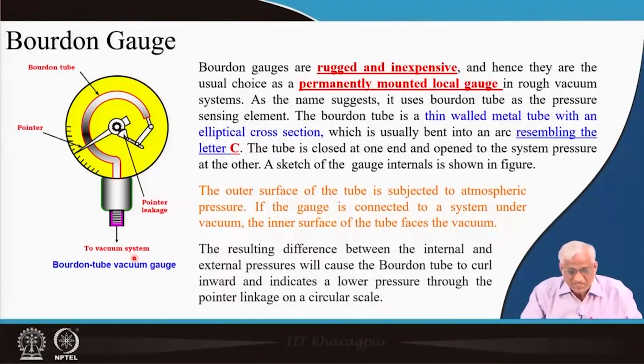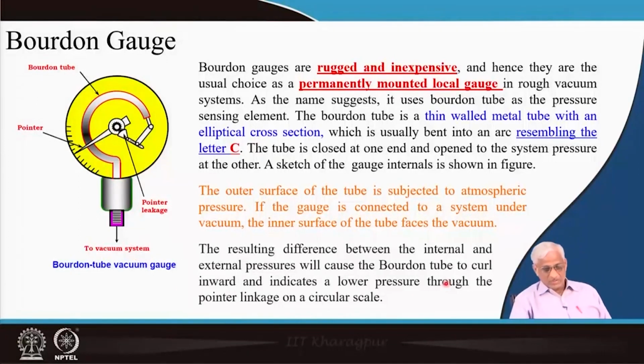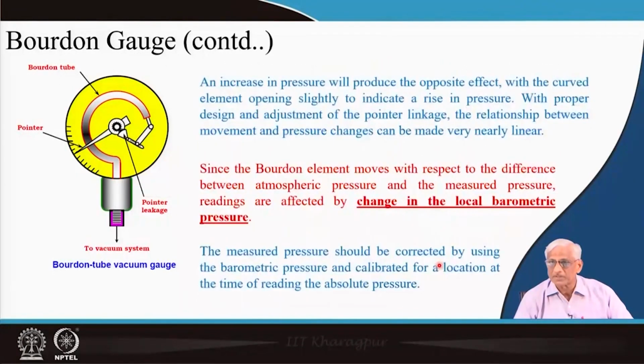So these deflections are finally measured and calibrated using a primary sensor like a U-tube manometer at fixed points. Then you can use it left and right in a very rugged way. The resulting difference between outer and inner pressure is the fundamental principle, and that will be coupled to the linkage and a circular motion, with a scale.